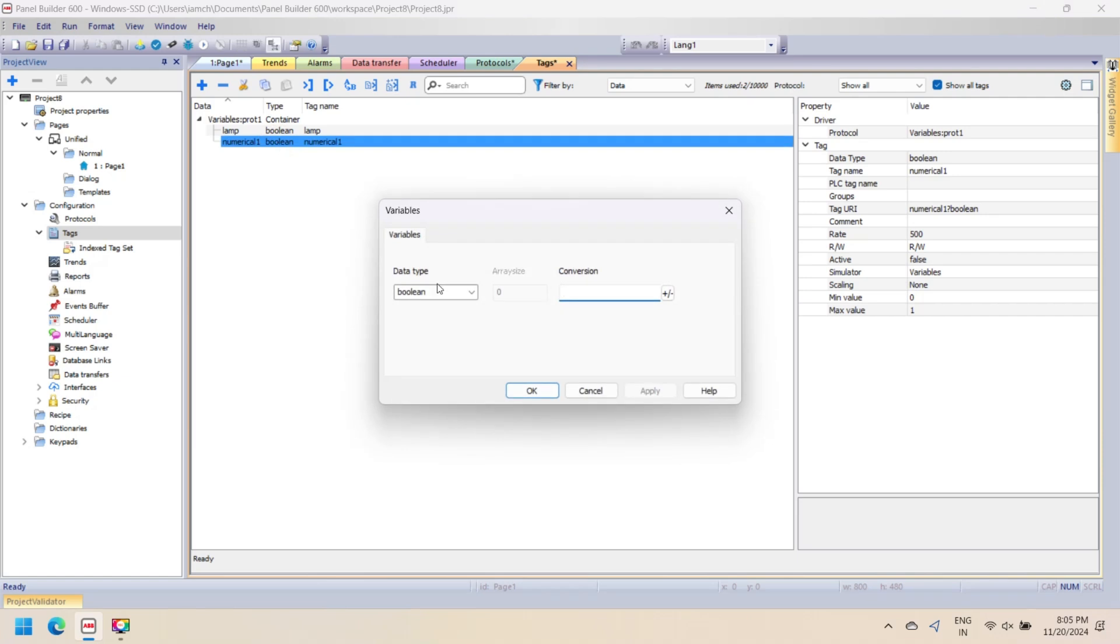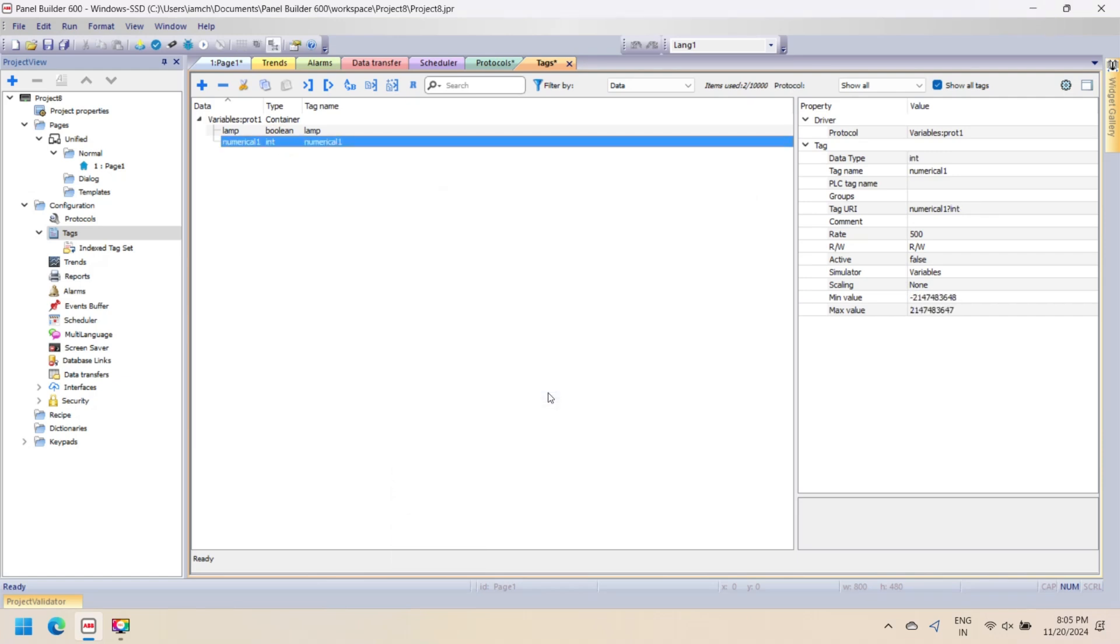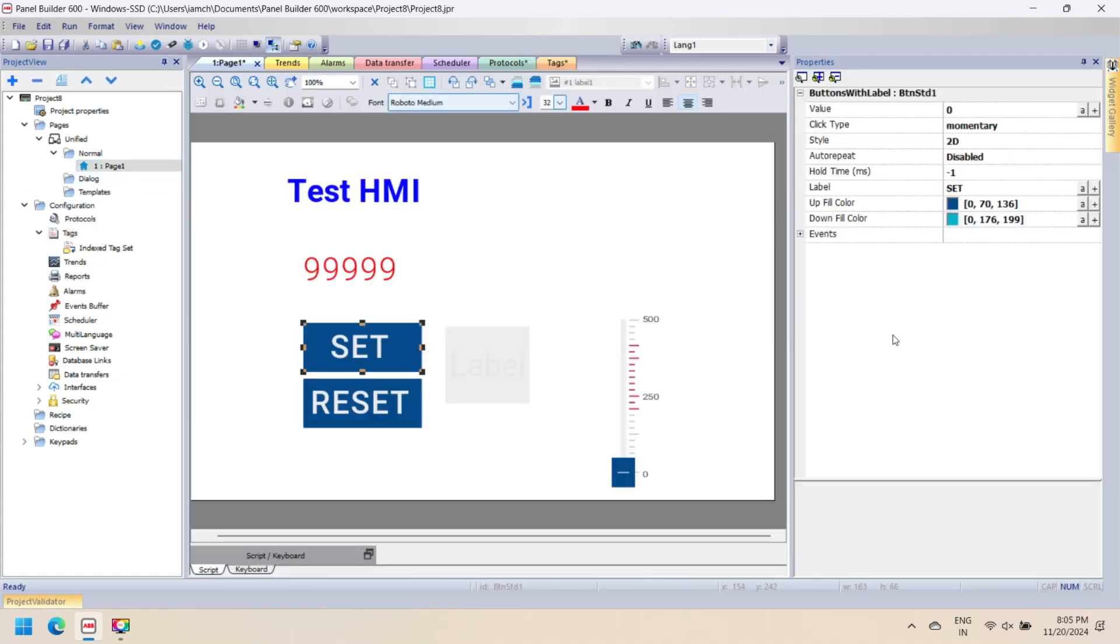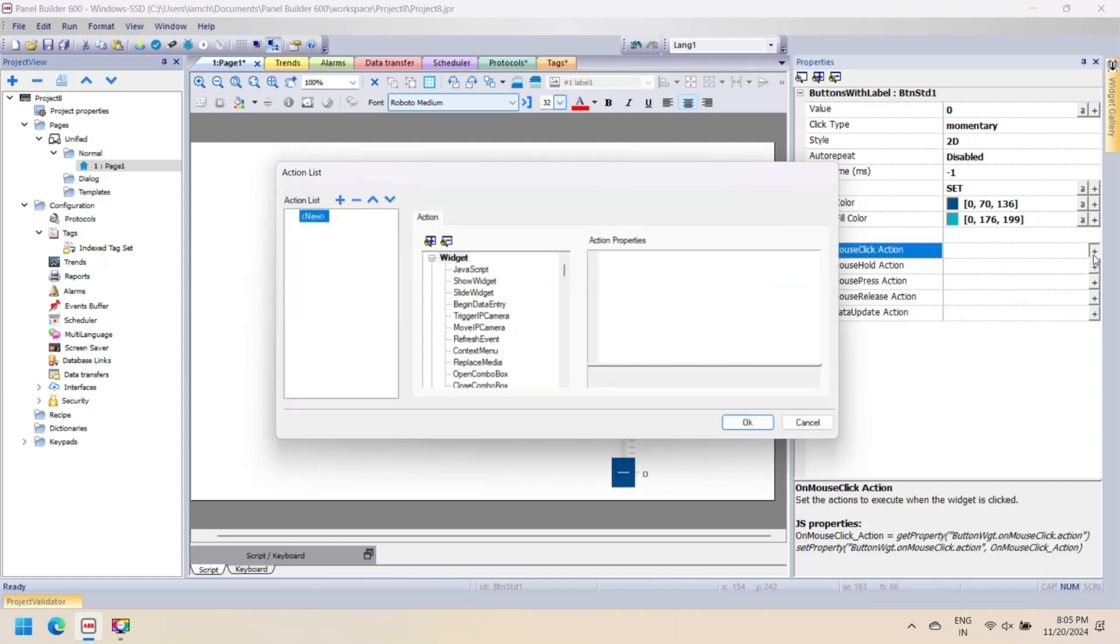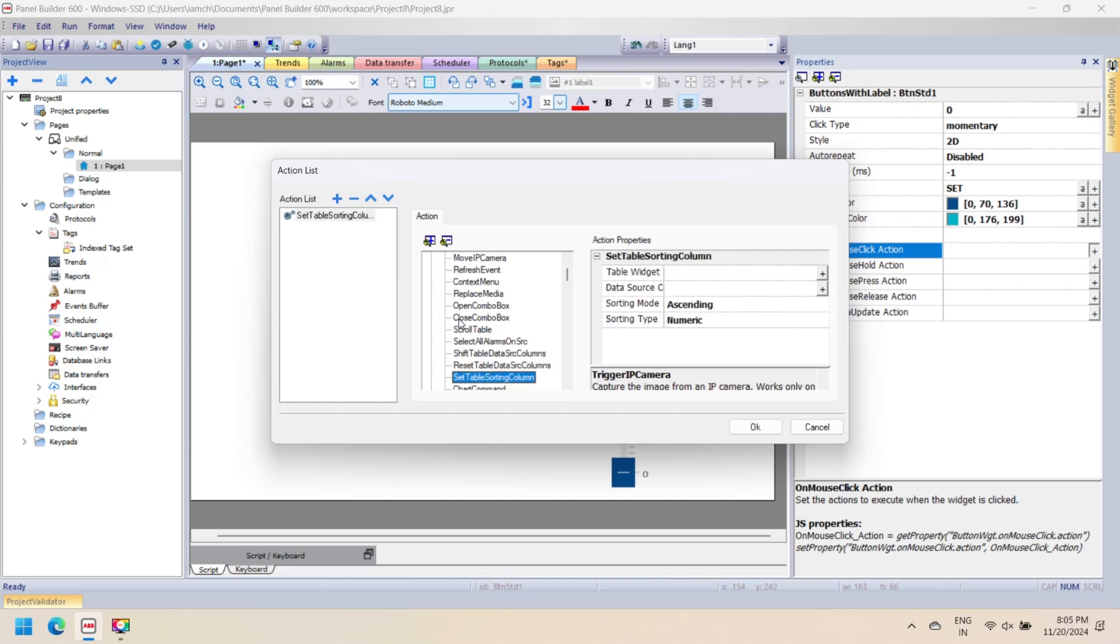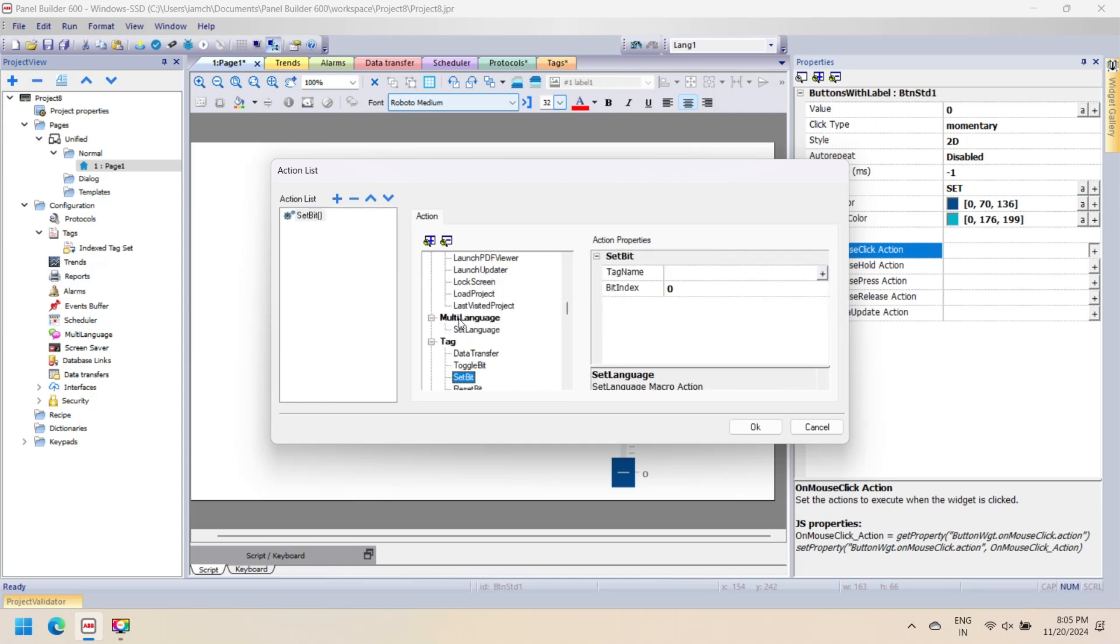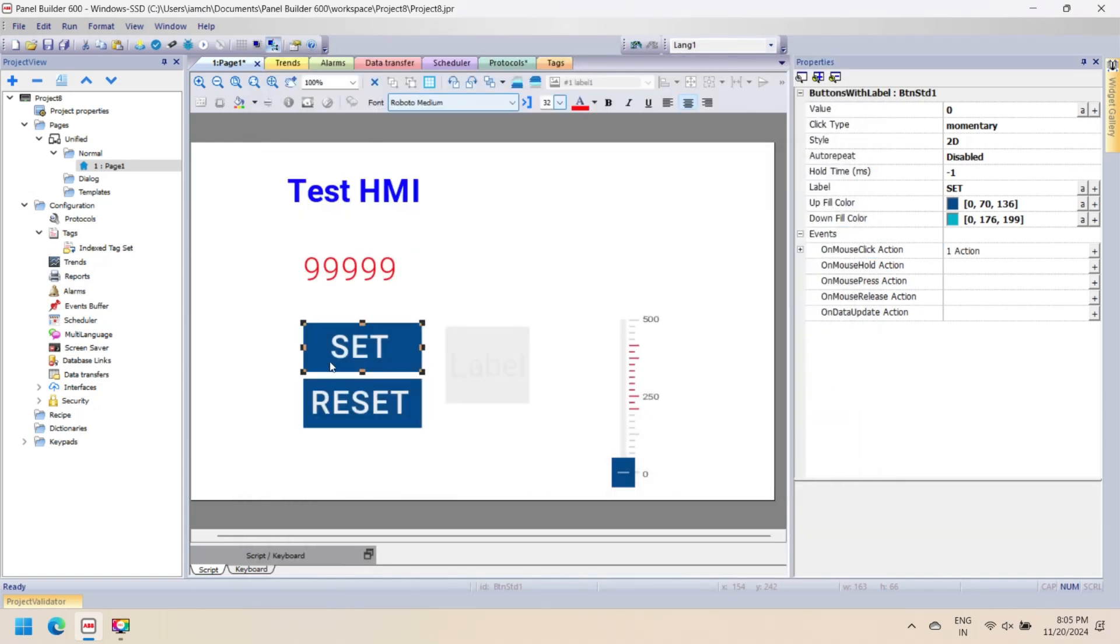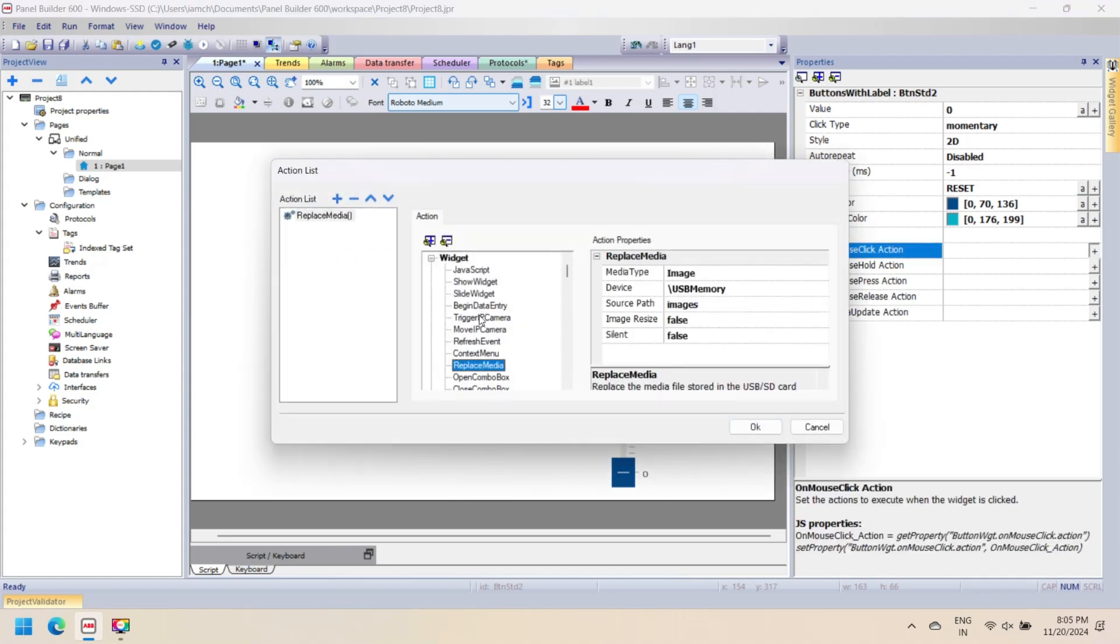After adding components, now declare events for your components. To do so, select a component and in the properties window select an event. In this video we set an event to the button: when the SET button is pressed, the light turns on, and the RESET button turns off the light or resets the tag value. Numerical values are assigned to the numerical input and tag. Select the button, then in the button properties select the mouse click event to open the action dialog box. Here select the Set Bit action and select the tag you want to set when clicking the button. Repeat the same procedure for the RESET button. The Reset action resets the bit of the selected tag.